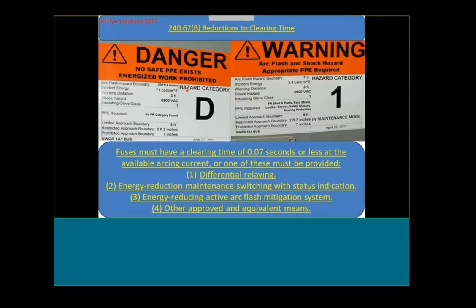So what they did is they put in an energy reduction switch. And by the way, something like that is going to be required in 2020. It reduced the arc flash hazard boundary from 200 feet down to 7 feet, and the energy from 71 calories down to 3 calories. Look at the equipment I need to wear: fire retardant shirt and pants, face shield, gloves, safety glasses, and hearing protection.